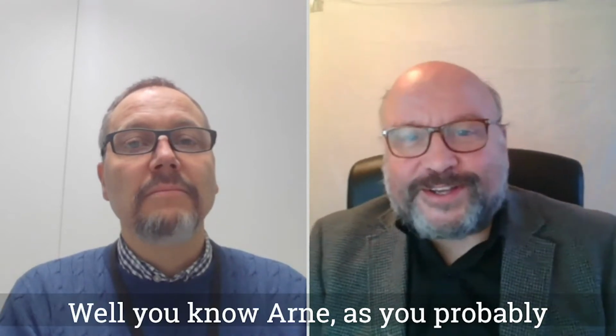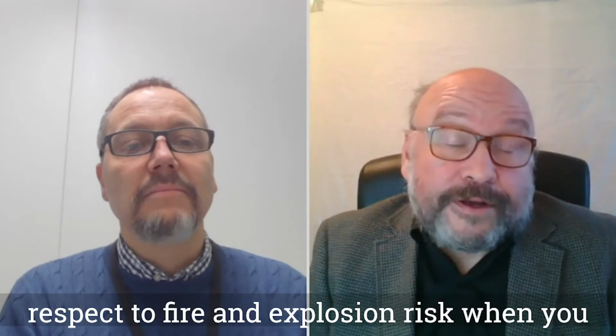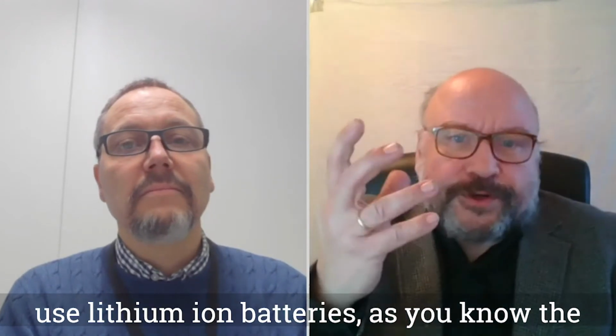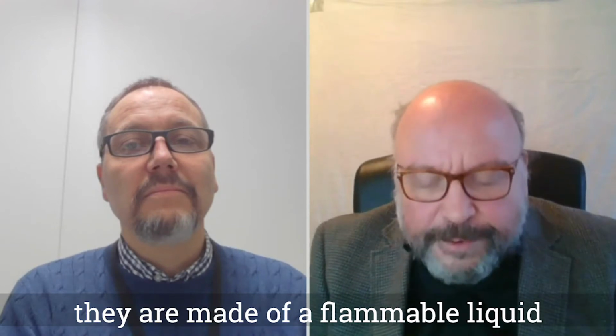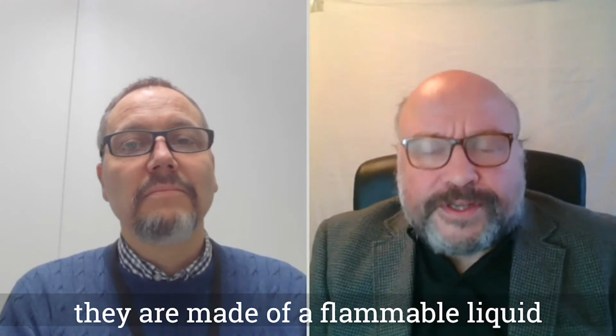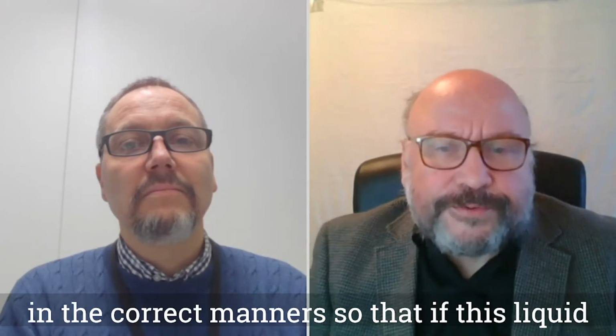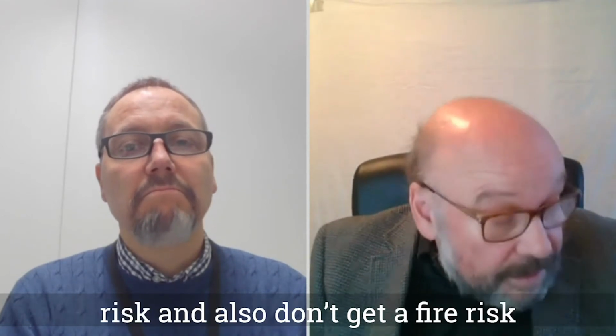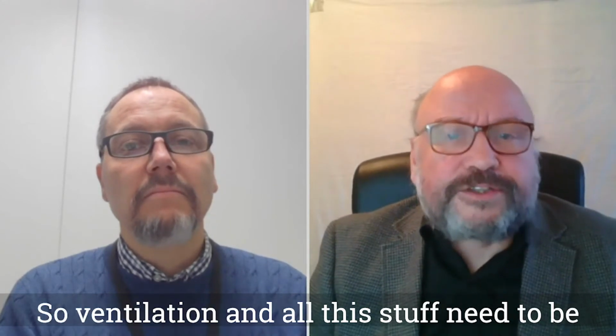Yeah, well, Arne, as you probably also know, there is a challenge with respect to fire and explosion risk when you use lithium-ion batteries. As you know, the electrolyte inside these fantastic batteries is made of a flammable liquid. So it's very important that you install it in the correct manner so that if this liquid is coming out, you will not get an explosion risk and also don't get a fire risk. So ventilation and all this stuff need to be in place.